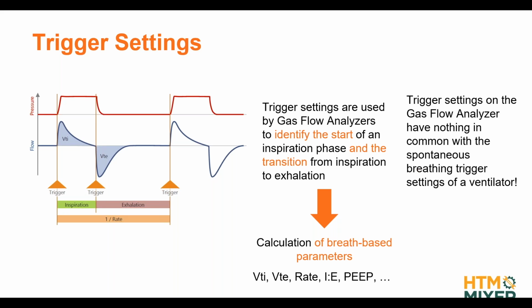One last remark here: the term trigger settings, you will also see that on your ventilator. But be aware that this is something completely different. It has nothing in common. The trigger settings on a ventilator are there to set the sensitivity for the ventilator to trigger spontaneous breathing of the patient. So if the patient tries to inhale and that flow reaches, say, 2 liters per minute, or if I have a pressure drop of 1 centimeter, then I want to trigger a supported breath by the ventilator. So this is really not to be confused. Some people call us and say, hey, my trigger settings on the ventilator are like this, does that relate to trigger settings on my analyzer? Not at all. It's something completely different.